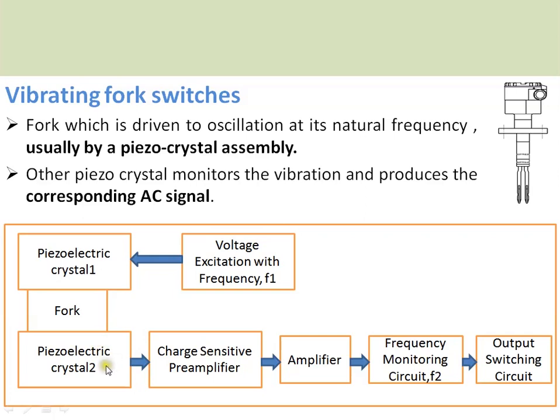The monitoring crystal generates a charge which is converted to a voltage by a charge sense preamplifier, then amplified by an amplifier. Since it is an AC signal, it is monitored by a frequency monitoring circuit. There is an output switching circuit that responds to changes in frequency — it can change a relay, or provide an NPN or PNP output that can be connected to a PLC.